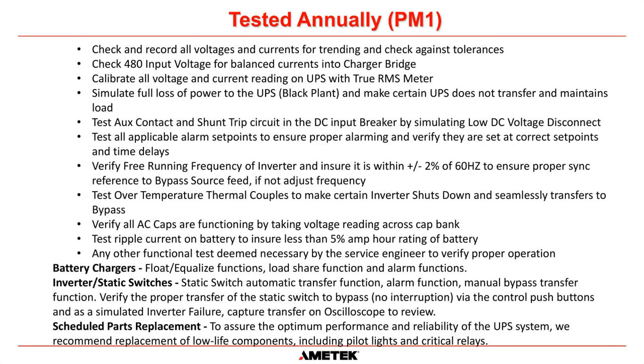So we have to verify that that circuit works, and we do that during the PM. We also test all the applicable alarm set points to ensure that all the alarms work at the voltages with the time delays and the correct set points that they should do. And we refer to the factory test data to make sure that they are all as they should be.